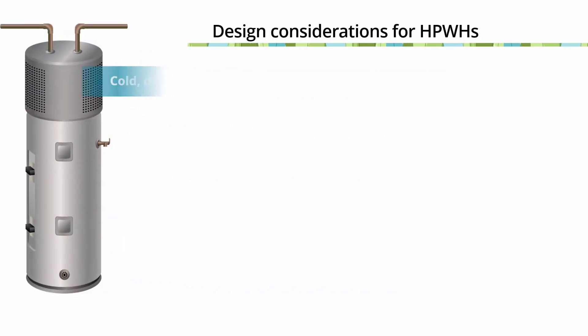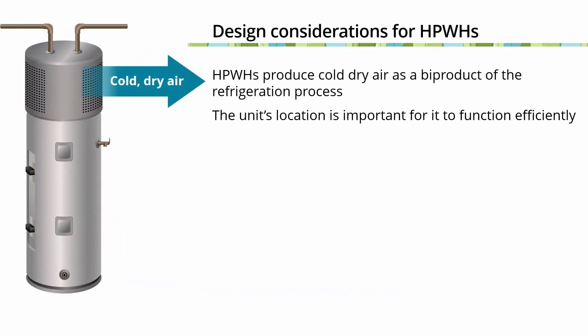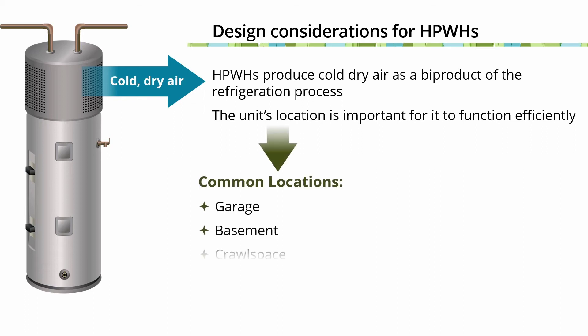Additional design considerations for selecting a heat pump water heater are based on its functionality. Since heat pump water heaters extract heat from the surrounding ambient air and produce cold and dry air as a byproduct of the refrigeration process, the location of the unit is important for it to function efficiently. Common locations include a garage, a basement, or a crawl space. These spaces are sufficiently buffered from outdoor ambient air temperature, and the cold, dry air produced by the unit is generally acceptable. In colder climates where temperatures fall below freezing, locating a heat pump water heater inside conditioned space is a viable option, although it's important to consider how to evacuate the cold, dry air it produces.